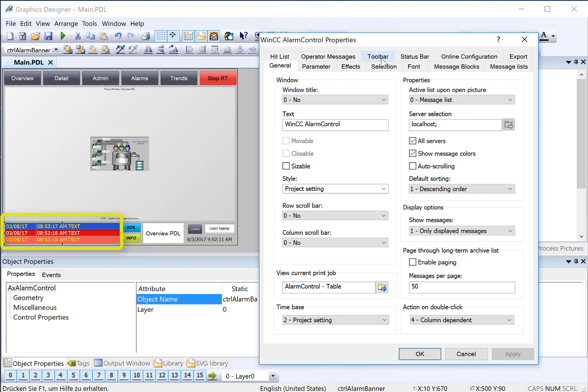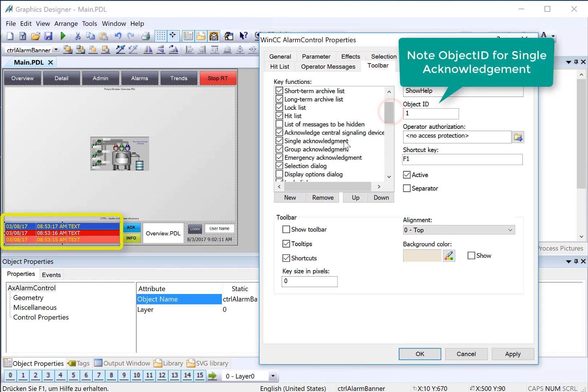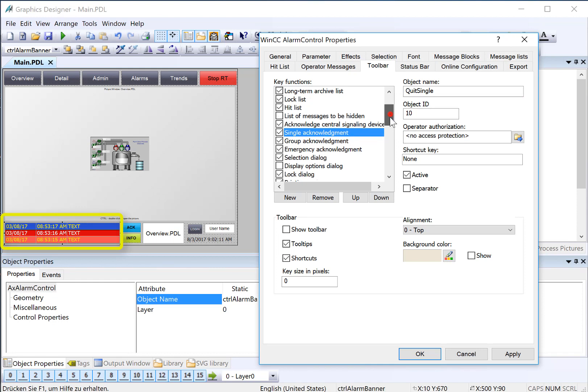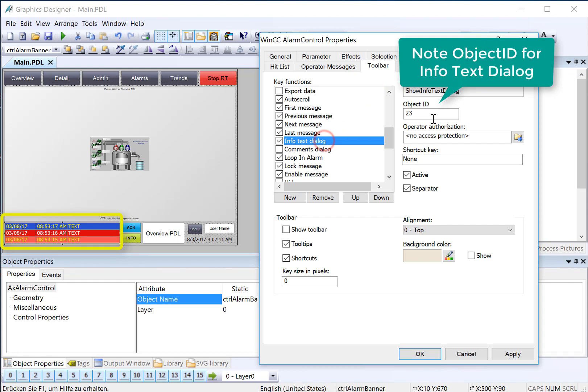The second piece of information is on the toolbar tab. We find the button we want to duplicate the functionality of and note the object ID. We can use this to duplicate that functionality using a direct connect. Single acknowledgement is 10, and InfoText dialog is 23. We can just hit OK here.